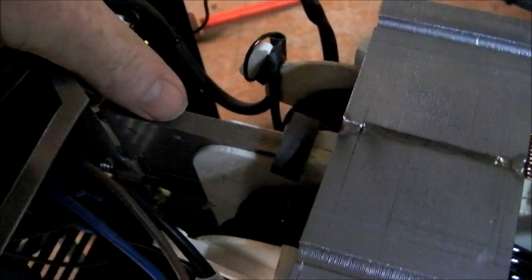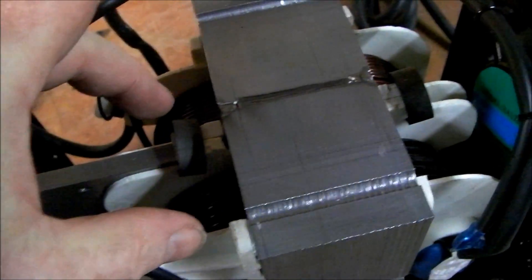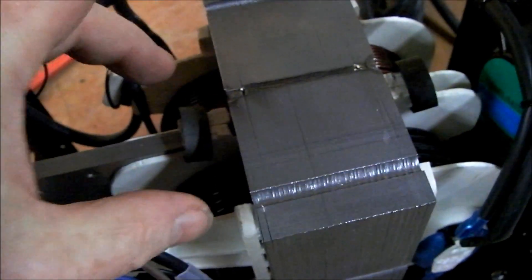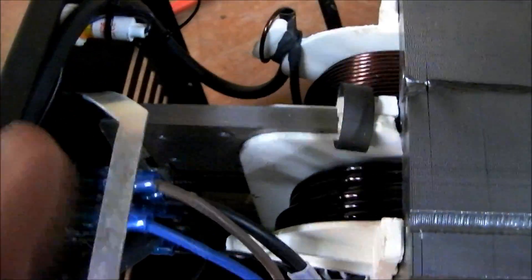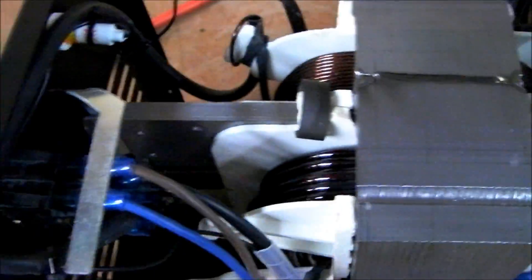This is just a little piece, leaves of metal that are screwed in and out between these two coils here. And they interfere with the magnetic field. So that's how you adjust your amperage. So this just gets screwed in and out. Now what's actually happened to this of course is this is busted. So I'm going to have to find out what's wrong with it. So I'm going to have to take this transformer off.